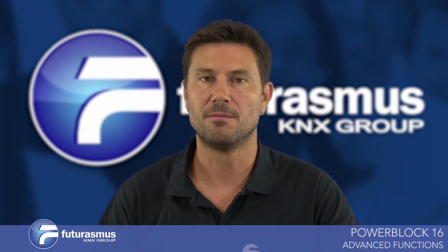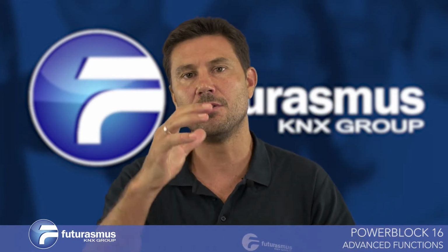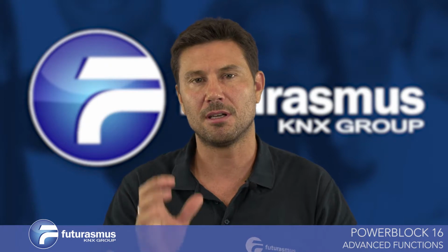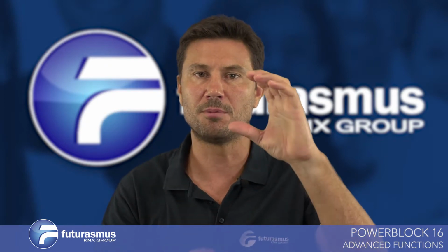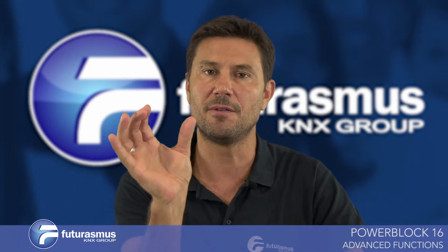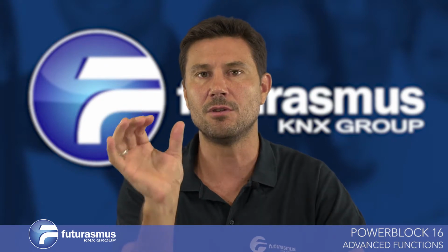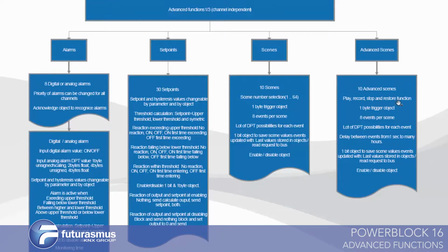Okay, the actuator has 2 scene modules. These scene modules are totally independent modules with its own input objects and its own output objects. The output objects can be configured, and the input object in the KNX scene module is the standard KNX input object. And in the advanced scene module, you can decide the data point type of this object, and you can decide the value it should receive to play, record, stop, or restore this function.